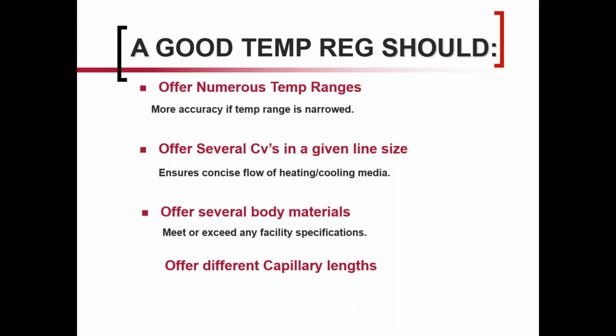And this is big, anyone that has experience in any type of valve sizing and selection, be it mechanical pressure regulators, control valves, electrically actuated control valves, having the right CV is paramount to successfully applying the valve. And that's true with Mark 80 with temperature regulators. Having the right CV so that if it's a heating application, you get enough steam through the valve when it's open to maintain the heat. If you're oversized, you might allow too much steam through, or if it's a cooling application, you might let too much glycol through. So having several CVs in a given line size is very important.